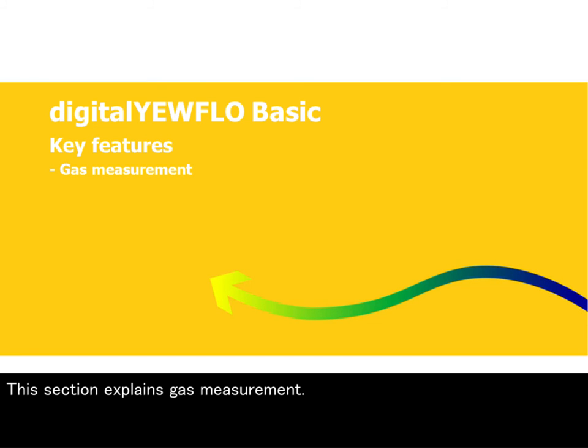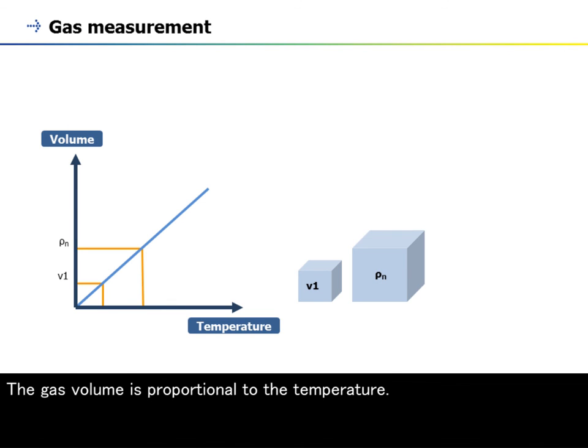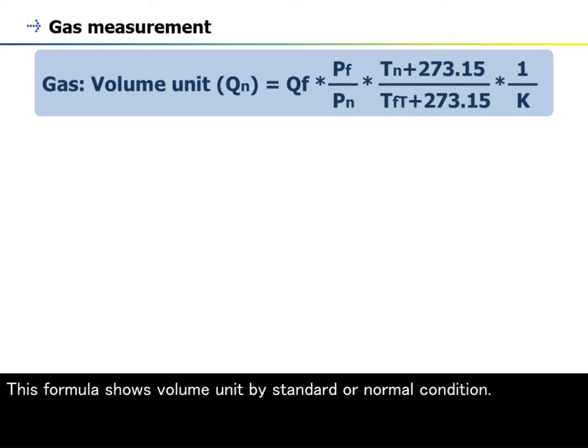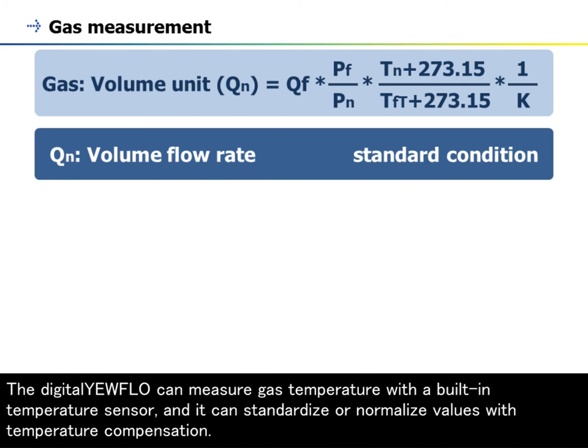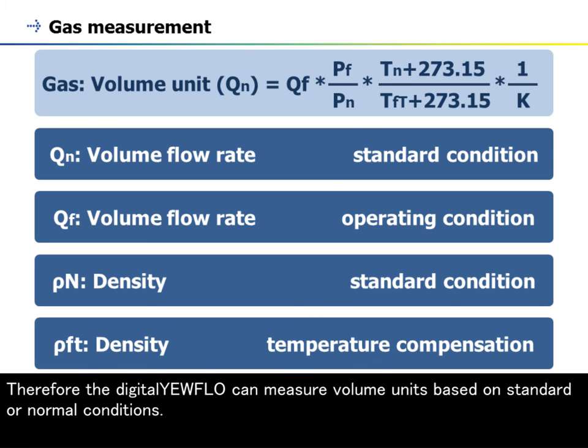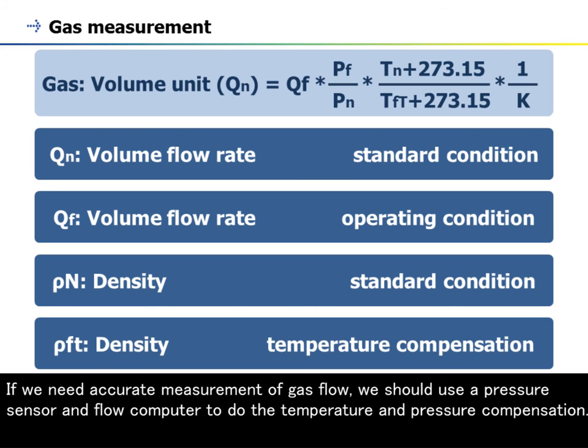This section explains gas measurement. This graph shows volume versus temperature in gas. The gas volume is proportional to the temperature. If we need units of volume at a standard or normal condition from operating condition, we should standardize or normalize it through temperature compensation. This formula shows the volume unit by standard or normal condition. The digitalYEWFLO can measure gas temperature with a built-in temperature sensor, and it can standardize or normalize values with temperature compensation. Therefore, the digitalYEWFLO can measure volume units based on standard or normal conditions. In this case, the digitalYEWFLO uses fixed pressure values for the calculation. If we need accurate measurement of gas flow, we should use a pressure sensor and flow computer to do the temperature and pressure compensation.